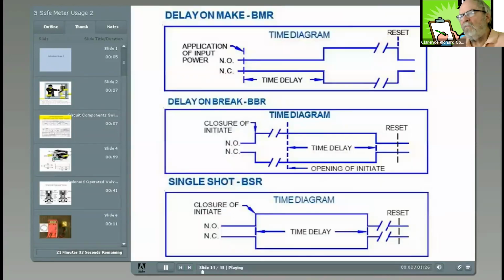Delay on make, BMR. Upon application of power to the input terminals, the time delay begins. At the completion of the pre-selected time delay, the output contacts transfer. Reset is accomplished by removal of input power. There is no false output when reset during timing.